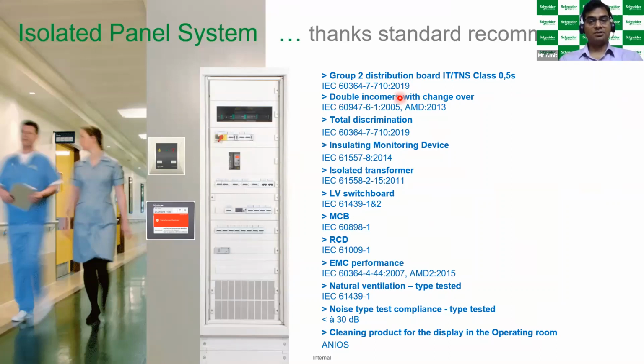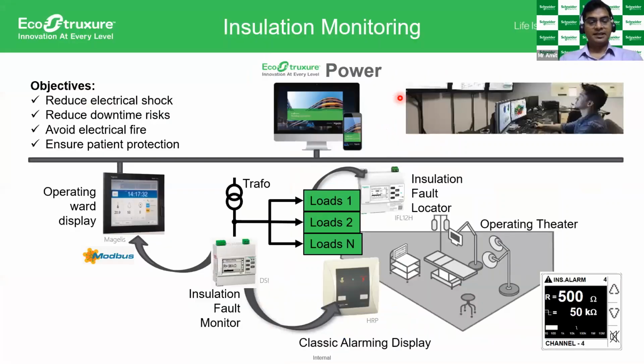So how to protect the human being? In such a case, there is a dedicated device called an insulation fault monitoring system that you can mount individually on the different loads, like the diathermy machine and suction machine. If anything goes wrong, like a nurse is providing supply in any of the sockets and the socket has a leakage issue, how will the doctor get to know there is some issue, so that the patient will be secure at that time?